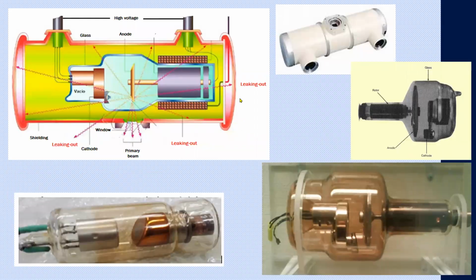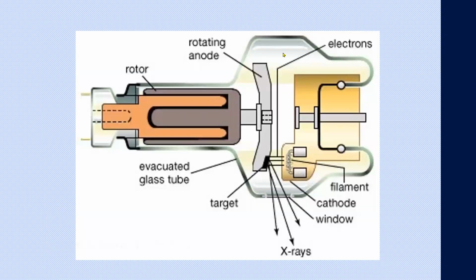All these machines have in common the X-ray tube. And we can see there are very simple designs of X-ray tubes, and others that are more complex, but regardless of the complexity of these designs, the main parts of an X-ray tube are the cathode, where the electrons are produced, and the anode, where the target is. And in order to accelerate the electrons against the target, we use high voltages.